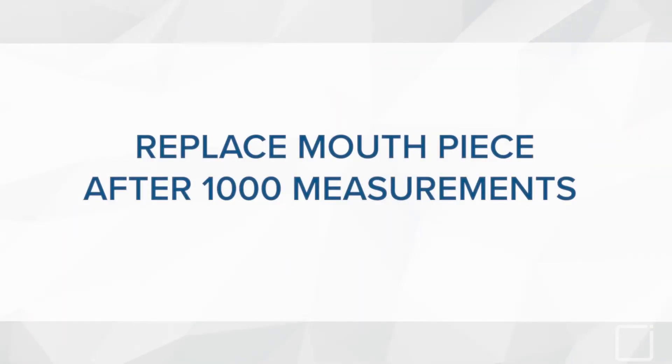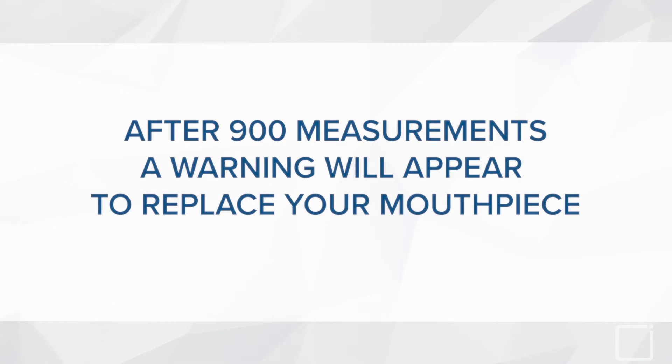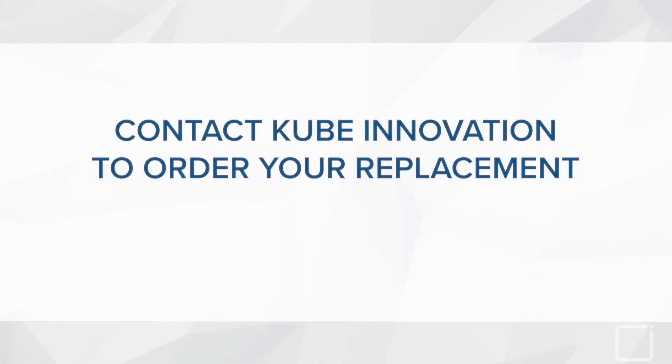In order to ensure accurate measurements, the mouthpiece must be replaced after 1,000 measurements. At 900 measurements, a warning will appear on the screen so you can contact KUBE Innovation to order your replacement.